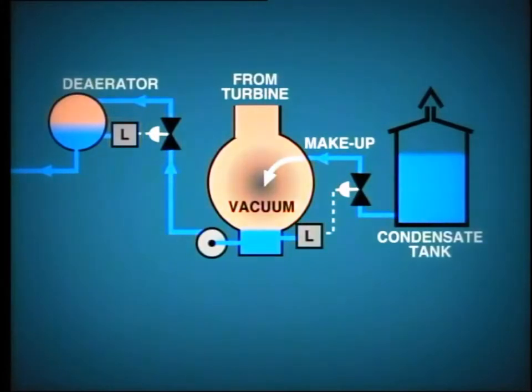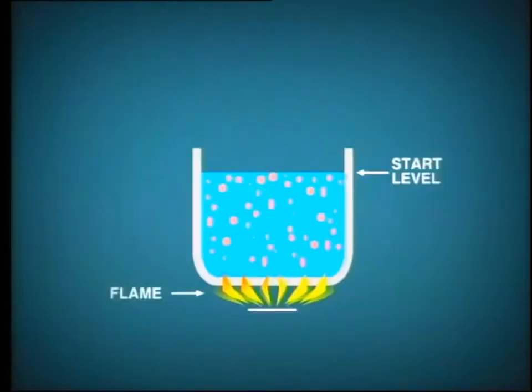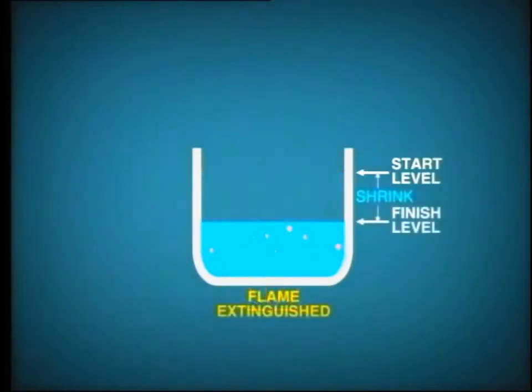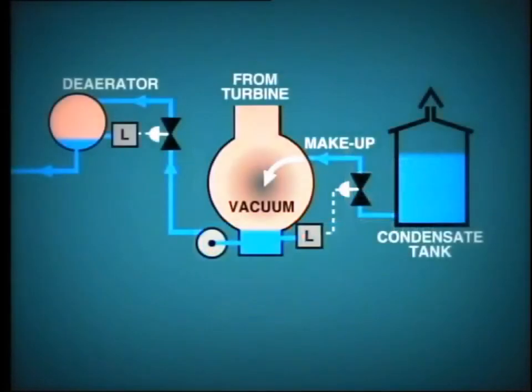Let's see how this simple arrangement works during a plant shutdown. As we begin to reduce load on the turbine generator and boiler, we find that the level in the deaerator begins to fall. The reason for this is that as the production of steam is reduced, a certain amount of shrinkage takes place in the boiler. Consequently, the boiler water level control system draws more water from the deaerator.